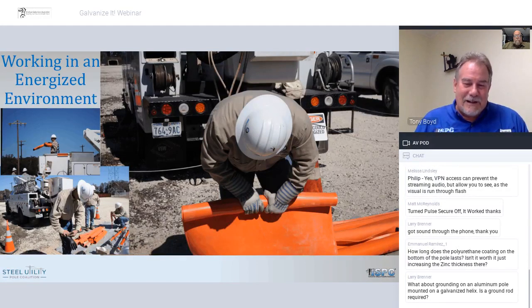And I said, no, you're going to put that in a bag and send it up the pole to me because I'm not going to overweight my bucket. So anyway, the point is, I came down and I said, well, I'm going to have to reach out past my rubber, so give me two more rubber line hose. And the guy on the ground said, no, that's fine, you're okay. And I said, no, you're not in the bucket. I am. So I'm going to cover the line up. So each job depends on what task you're actually doing as to how much cover. Jim and I will talk a little bit about some of the things that guys take for granted when working on wood poles that they should be doing, and we certainly should be doing it with the steel poles.